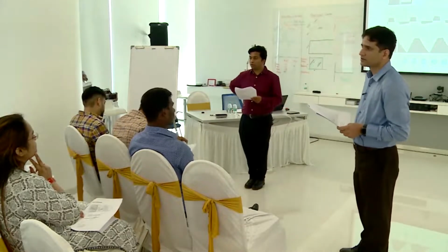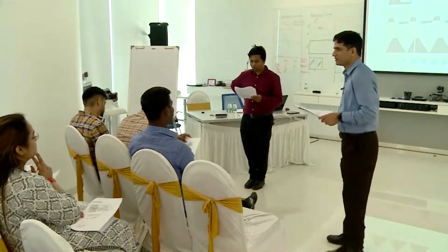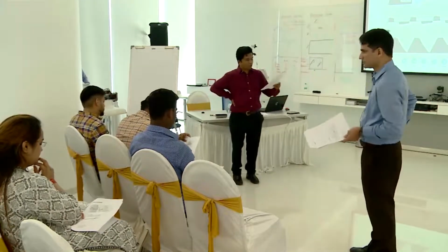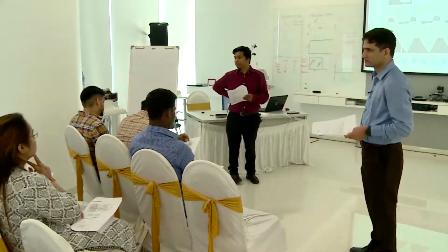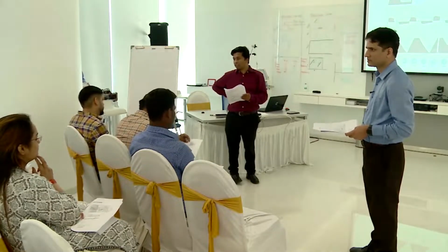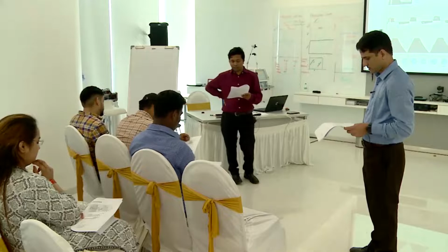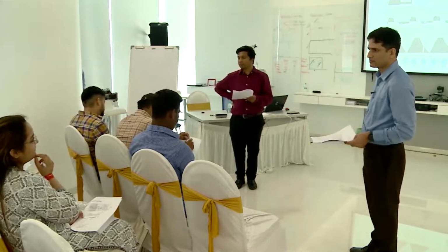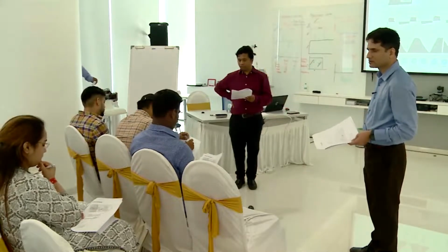Yes, VT. Very good. It's a volume time scalar. Look at the third graph. What is happening there? Leak. Very good. Because it is not touching the baseline. Next is what scalar? FT, flow time. Very good. So what is the problem here?